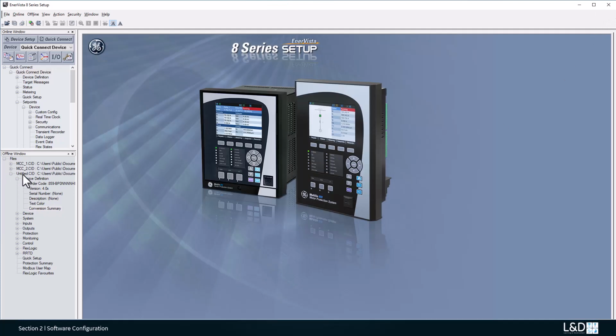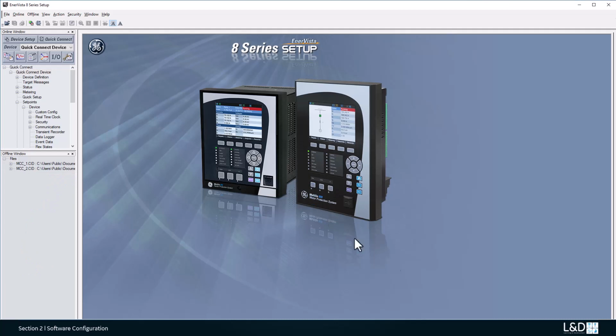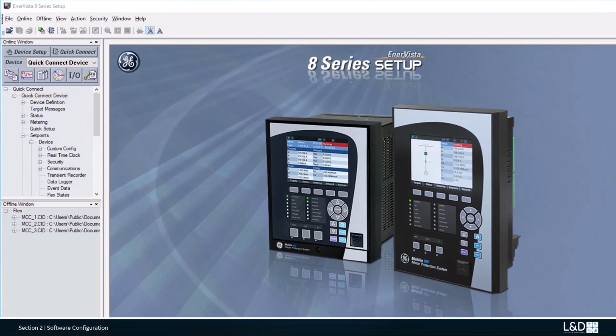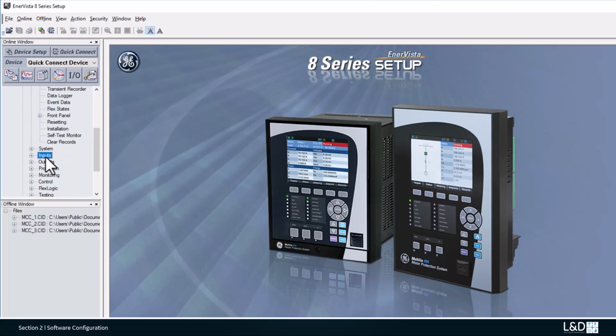And last, this setting file is using the default untitled name. If you want to rename it to MCC_3, we can right-click the mouse and choose rename setting file, and you can call this _3. So now we have 3 offline setting files in the offline window. The local digital inputs in the 369 are replaced by the contact inputs in the 859 with the default names.